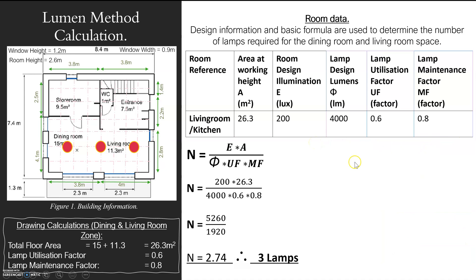Once I've got all that information, I'm just plugging it into the formula. E represents 200, A represents 26.3, my flux is 4000, and UF and MF go in there too. That gives me 2.74. Now that's not whole lamps, so I need to round that up. Always round up because N is the minimum number of lamps needed to satisfy this design's lux values given the lamp information.